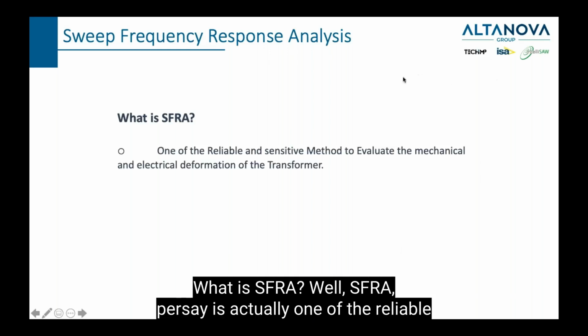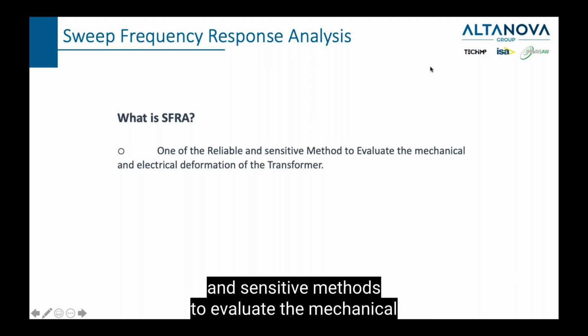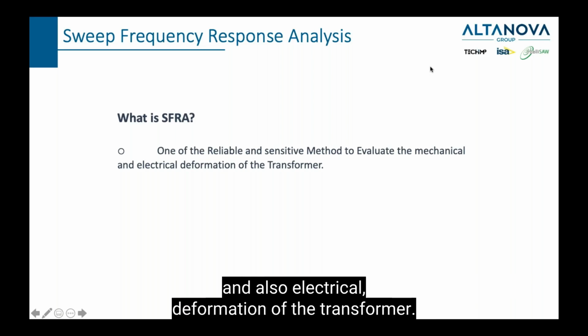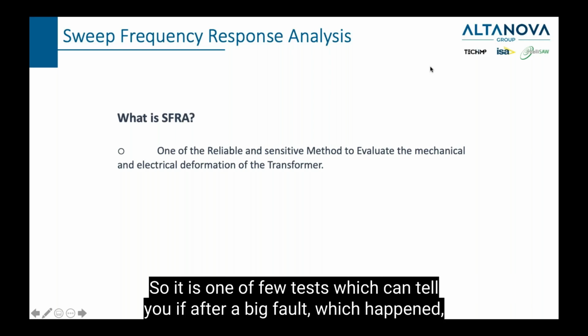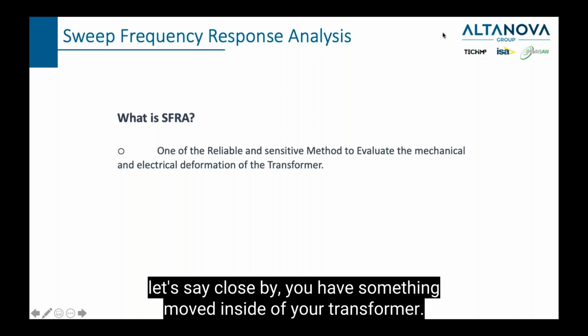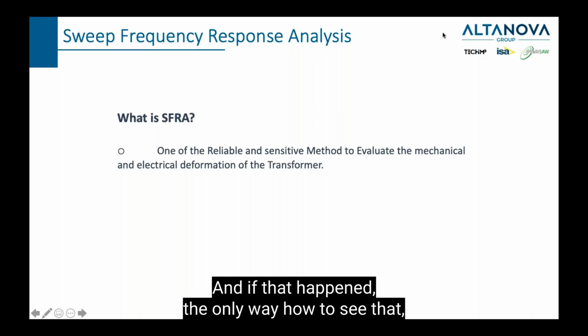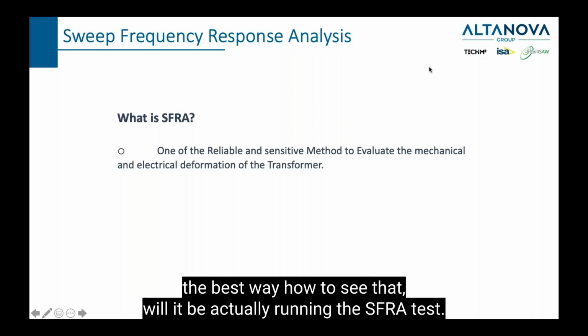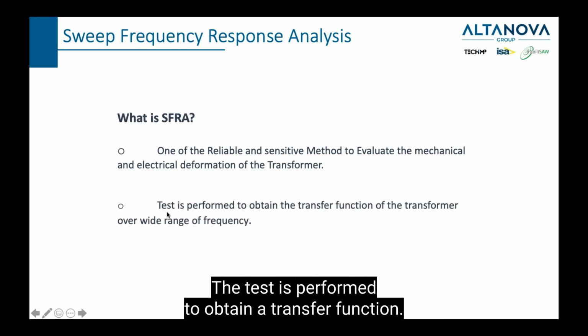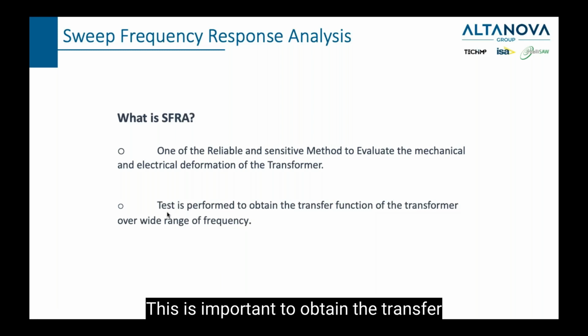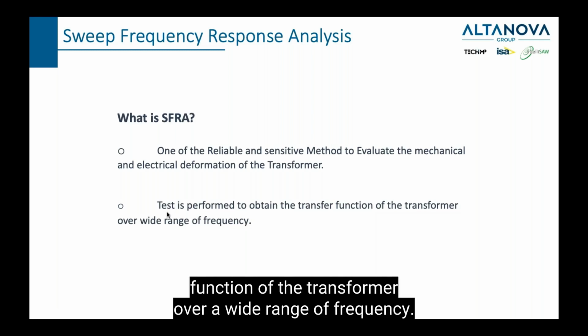What is SFRA? Well, SFRA per se is actually one of the reliable and sensitive methods to evaluate the mechanical and also electrical deformation of the transformer. So it is one of few tests which can tell you if, after a big fault which happened, let's say close by, something has moved inside of your transformer. And if that happened, the only way to see that will be running the SFRA test. The test is performed to obtain a transfer function. This is important, to obtain the transfer function of the transformer over a wide range of frequency.